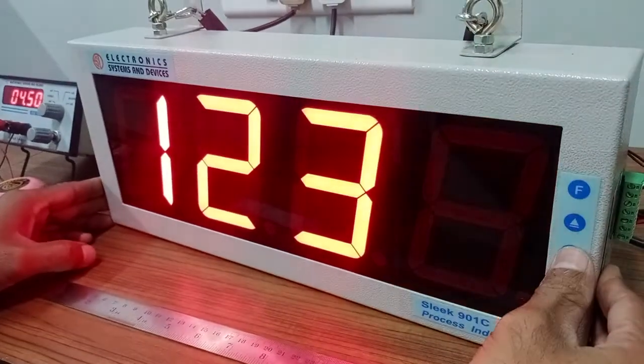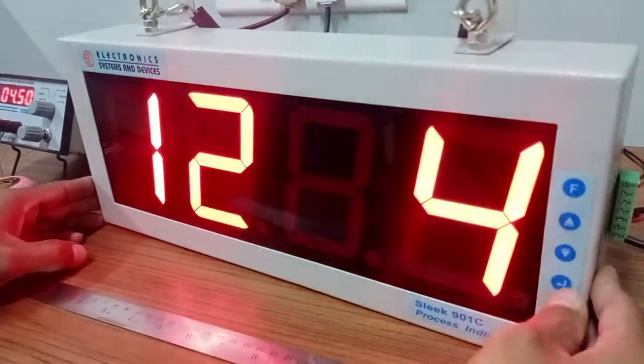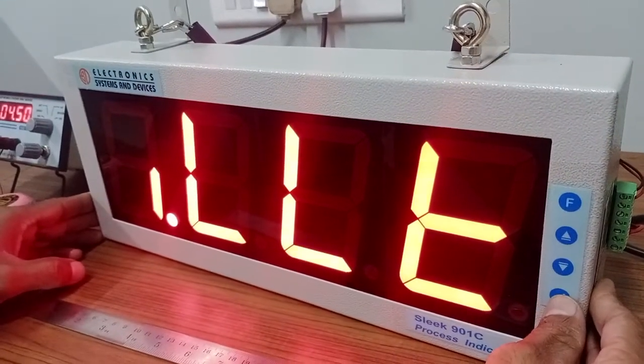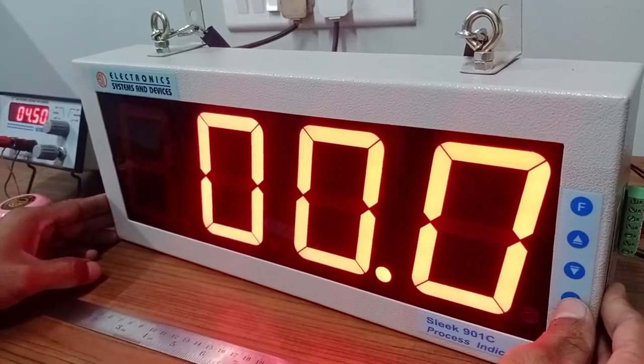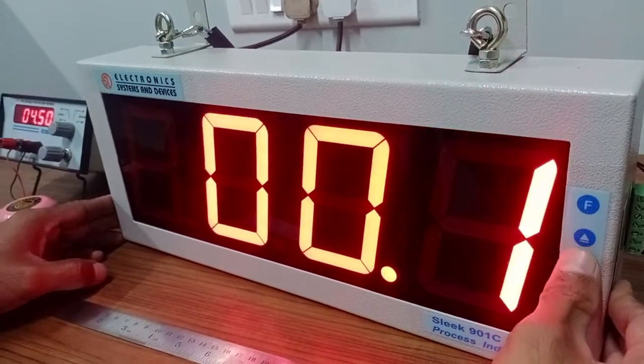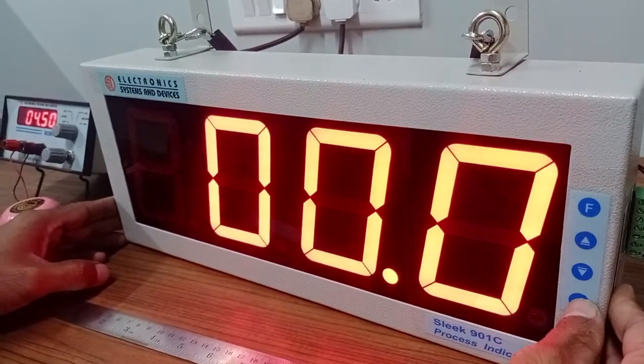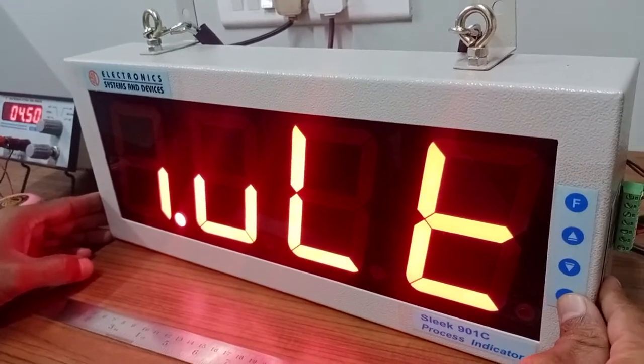Enter. This is input lower limit, so 4 milliampere, what it corresponds to, we have to feed it here. Right now we have kept it zero, you can change it. Enter. This is input upper limit, so 20 milliampere, whatever 20 milliampere corresponds to, you have to enter it here. We have kept it 1000, you can change it up to 9999.